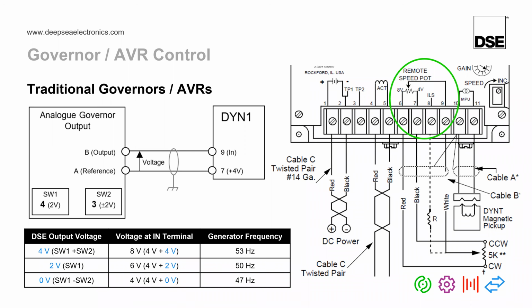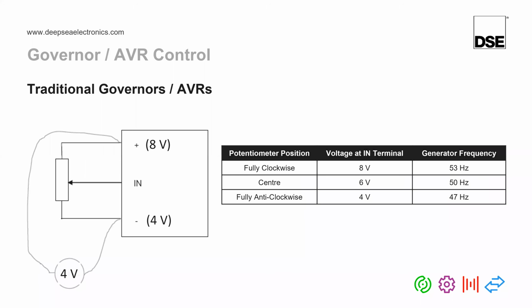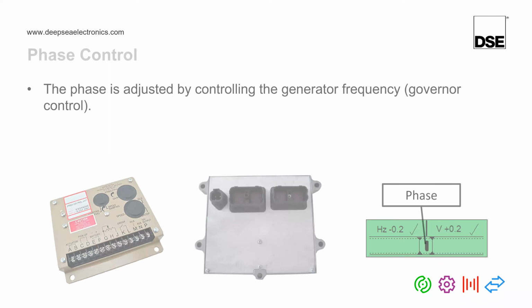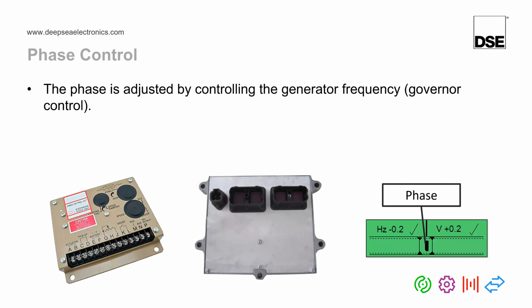The AVR controls voltage. Similarly though, if your generator is not running at the correct voltage, you will need to make adjustments on the AVR itself to run at the correct voltage. If I just go back a couple of slides to earlier in the presentation, I'll show you some of these potentiometers I'm referring to. The GAC governor is actually quite a good one. If we were to look at this GAC governor here, the potentiometer terminals that the DeepSea module would connect into are these ones here, G, H, and J.